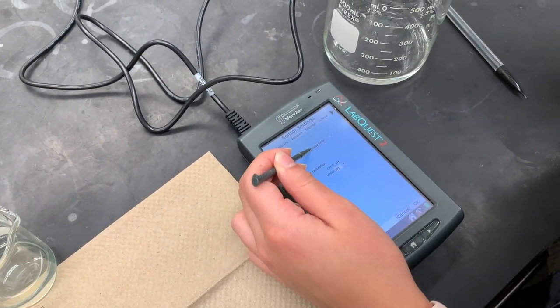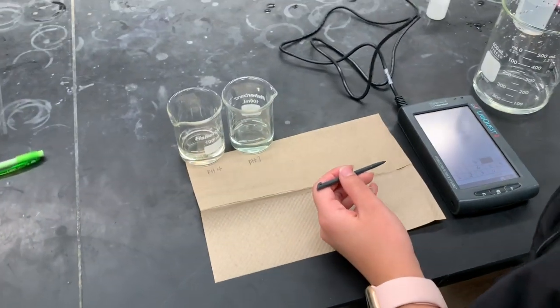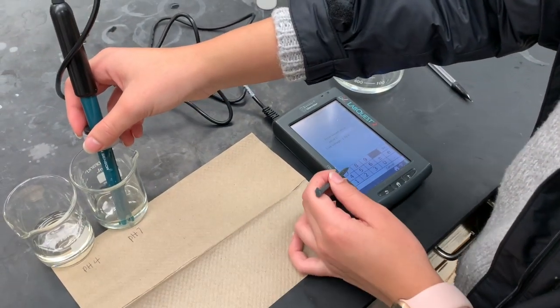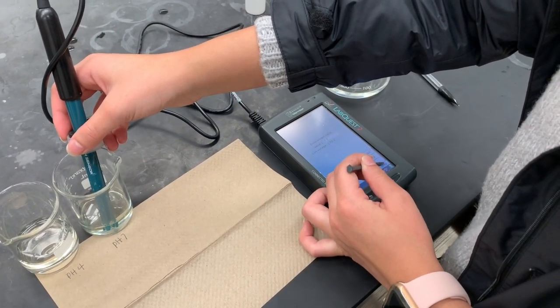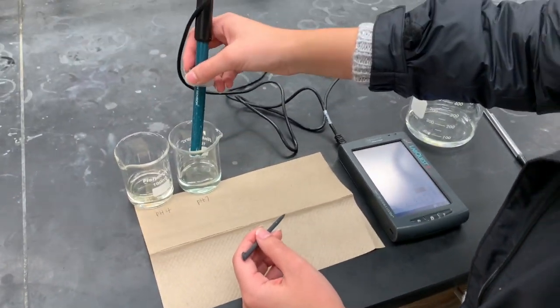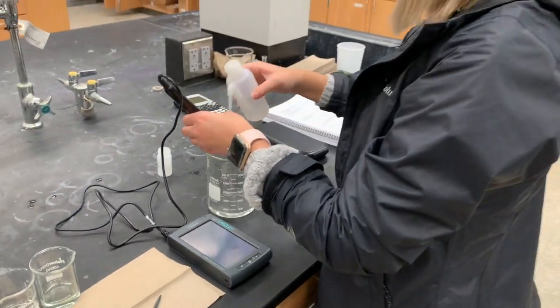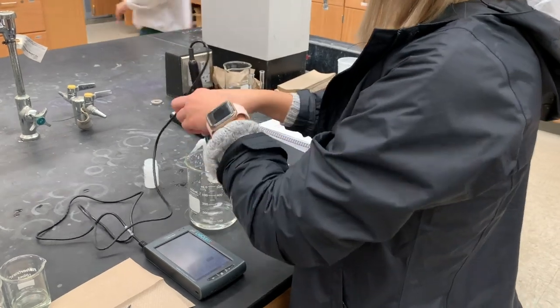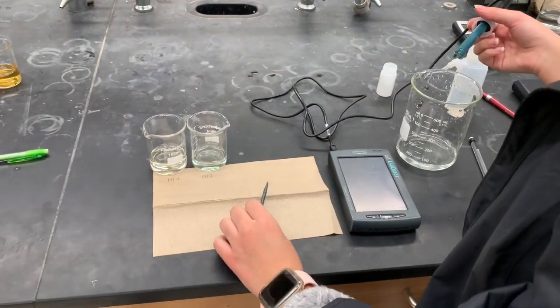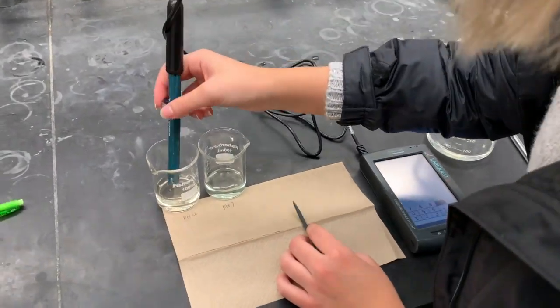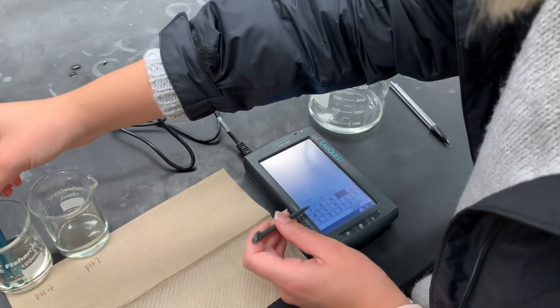Press Keep and begin the process again with the second buffer solution, starting with rinsing the probe with distilled water. Once you have completed this 2-point calibration process, you should place the probe back in a buffer solution to ensure it is reading correctly. After you are sure it is working properly, place the probe back in its storage container.